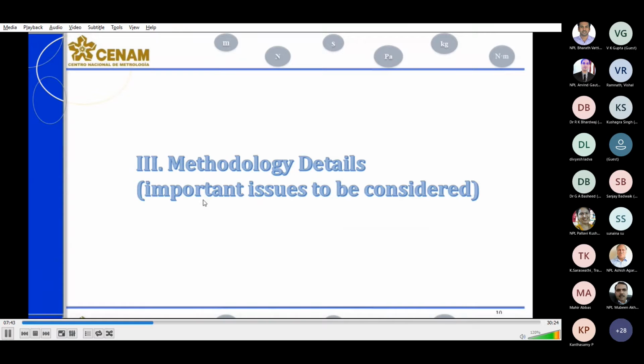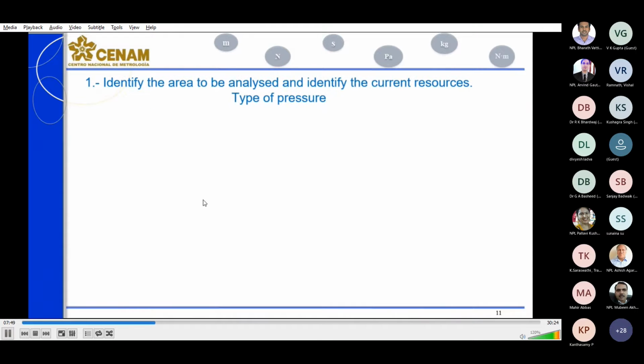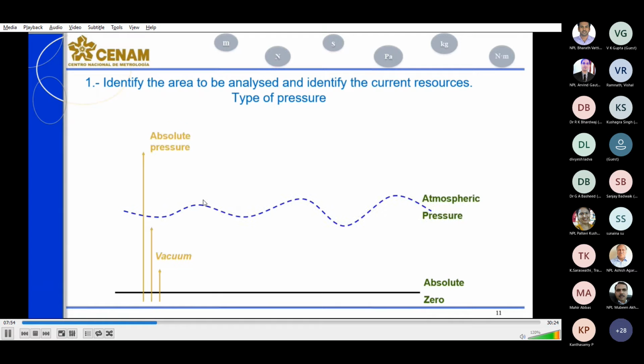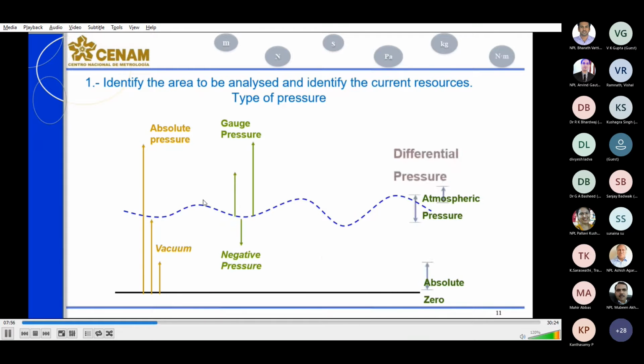We will look at the methodology details now. The first step is to identify the area to be analyzed and identify the current resources. That is the type of pressure. And as you may know, we have absolute pressure, atmospheric pressure, vacuum, and also we can measure gauge pressure, negative pressure. We can also measure differential pressure. So one pressure laboratory can do all those things or only one of those. The most common one is the gauge pressure.